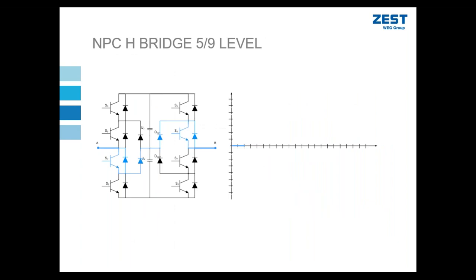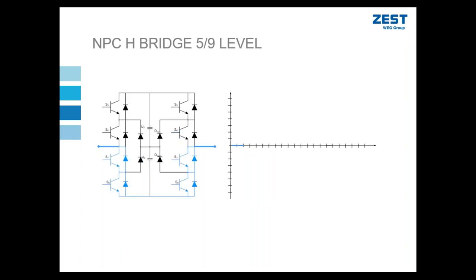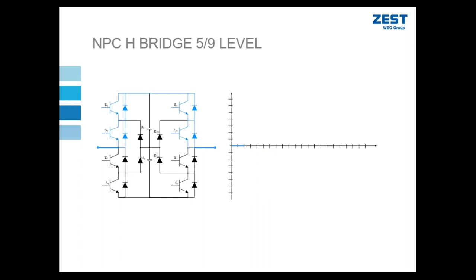Just to very quickly show you how the switching works for each power cell. That's very similar to what we've already covered. We can switch the two cells highlighted for zero voltage. We can switch the power cell shown for zero voltage or the power cell shown. So we've got three options for zero voltage in this case. Then we can do our first step by switching as shown. We switch those three IGBTs. We can increase that step by switching as shown. And so we can build up our steps to the motor.